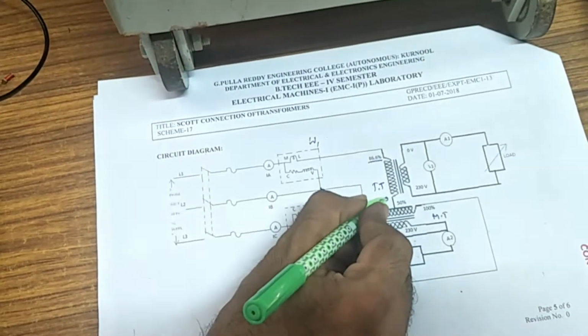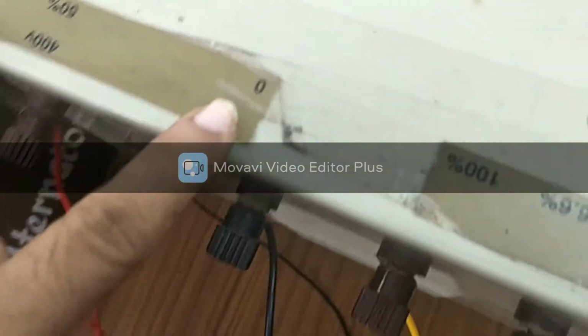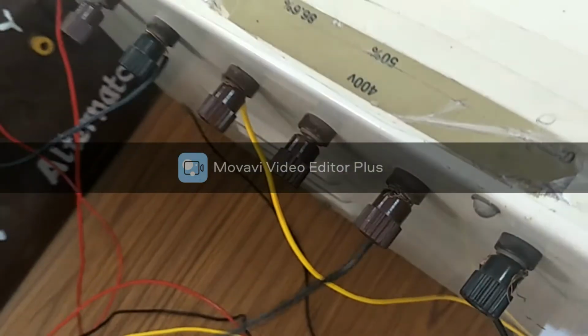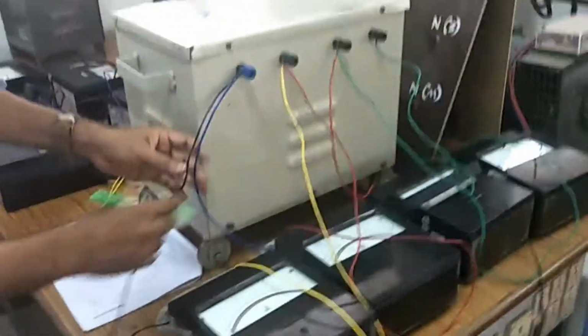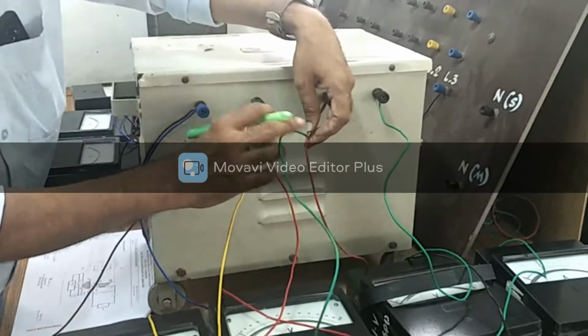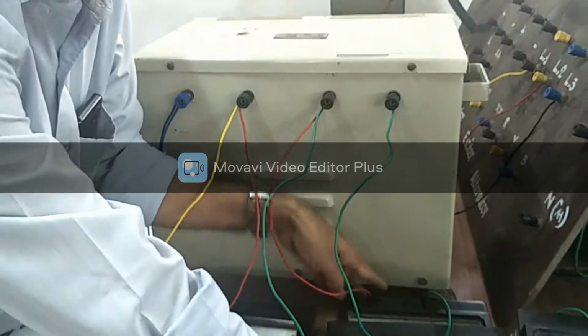See here, it is 100% turns, and you can observe L is connected to 100% of the main primary of the main transformer. Now see here, 0 of the teaser transformer and 50% of the main transformer both should be connected. These two are shorted. That's about the primary side of the Scott connection of transformers. Coming to the secondary side, let us consider the first transformer, the teaser side transformer. You just observe the wattmeter and voltmeter common and the ammeter common. These two are connected here.